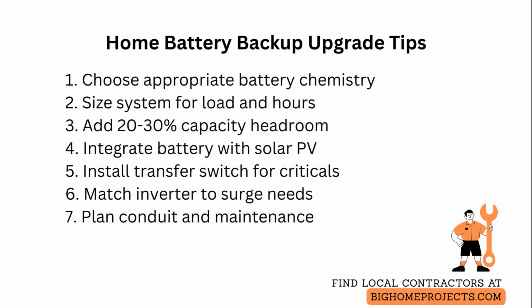Size the system by calculating continuous load watts for essential circuits and multiply by desired outage hours to get required kilowatt hours, then add 20 to 30% headroom for inverter inefficiencies and battery aging.